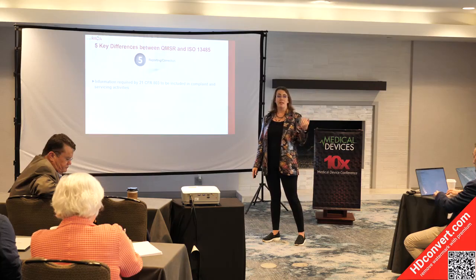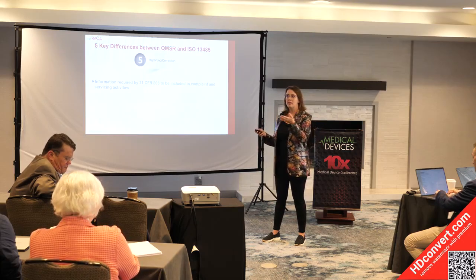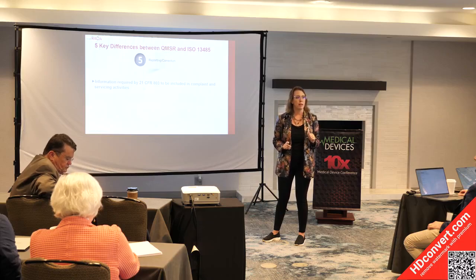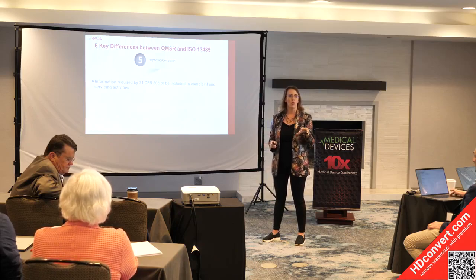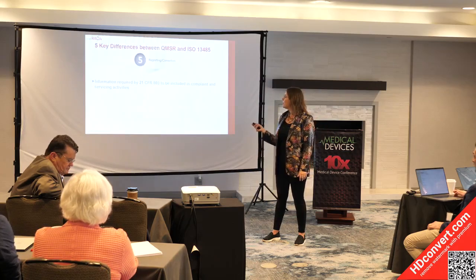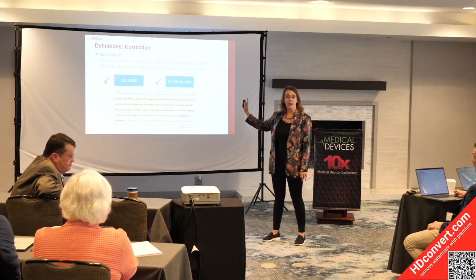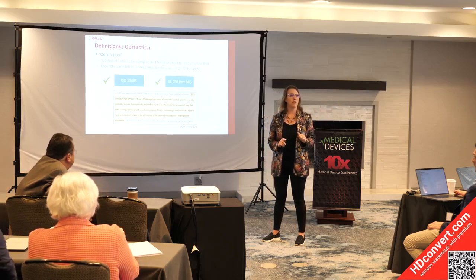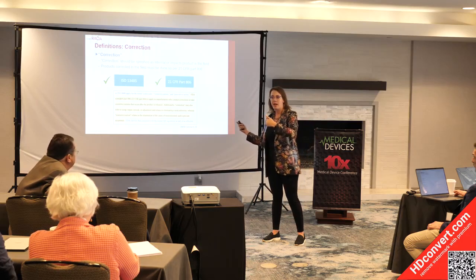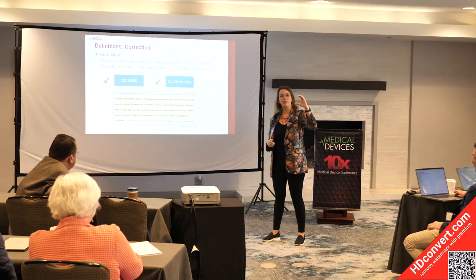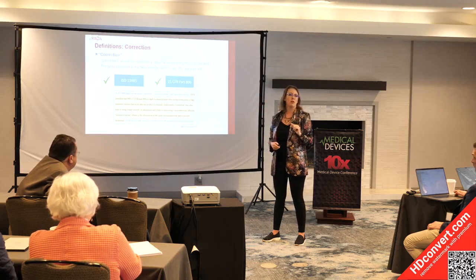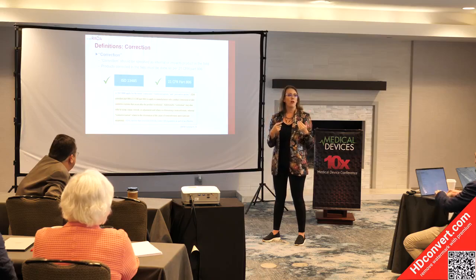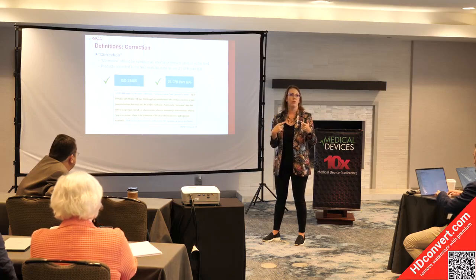This is where they're talking out of both sides of their mouth on 'corrections.' In FDA terms, a correction on product in the field means something very specific — it means you are taking action on product that has left your control. They are maintaining that concept from Part 806, but they are also adding the ISO 13485 concept of 'correction' within corrective and preventive action — covering product both in and out of your facility. It's going to be critical to differentiate whether 'correction' in a CAPA refers to product in your control or something you should have notified FDA about.